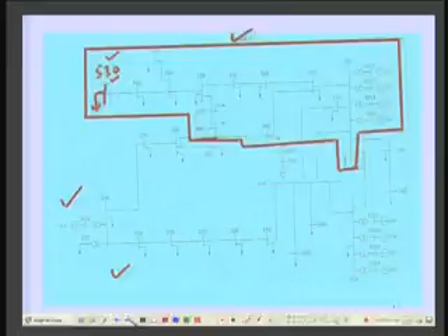You can see that this is one point on the graph, when the loading is about 80 plus megawatts. As you increase the load from 80 megawatts to 200 megawatts, the voltage at this bus, bus number 530, expressed in per unit, drops. It comes to point B, then point C. At point C, if the total load in area 1 comes to about 190 megawatts, you will find that the load flow will not converge. It means we have reached the critical operating condition, and beyond that, if you try to load the system, it will become unstable and voltage collapse will take place.